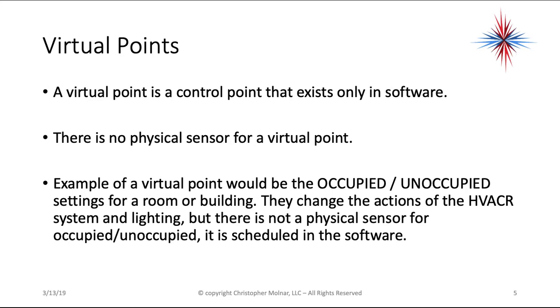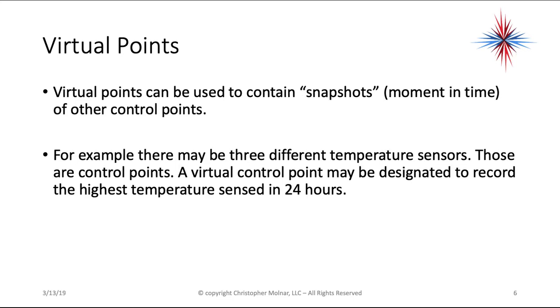A virtual point is a control point that exists only in the software — there's no physical sensor for a virtual point. An example could be the occupied and unoccupied settings for a room or building. They change the actions of the HVAC system and possibly lighting, but there's not a physical sensor for occupied or unoccupied — it's scheduled in the software. Virtual control points can also capture snapshots of other control points, such as recording the highest temperature sensed from three sensors over 24 hours.